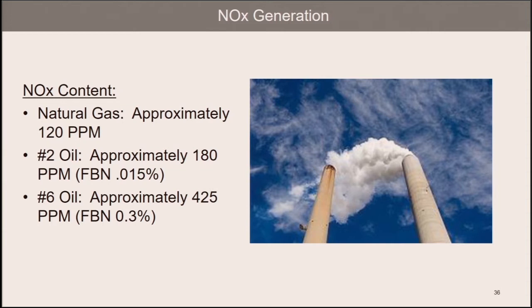No. 2 oil generates about 180 parts per million per pound with approximately 0.015% fuel-bound nitrogen, which we cannot do anything with in terms of reduction through thermal control. And for No. 6 oil, it generates about 425 parts per million per pound with 0.3% fuel-bound nitrogen, which we cannot remove thermally. So, getting rid of the fuel-bound NOx really requires a reformulated oil fuel — a synthetic — where the fuel-bound nitrogen is removed.